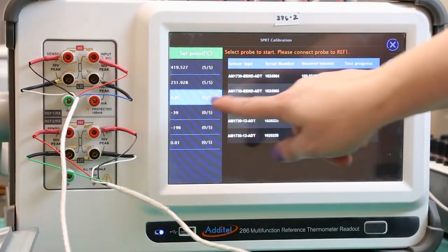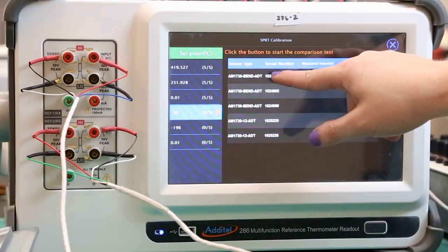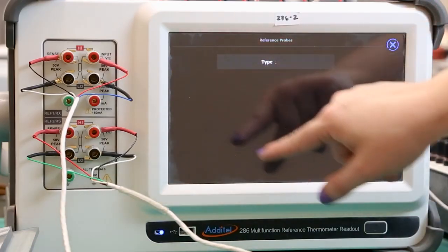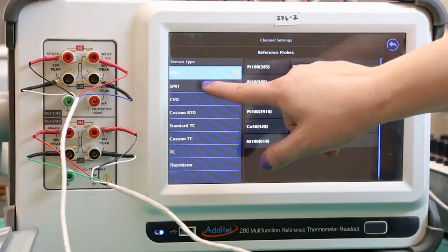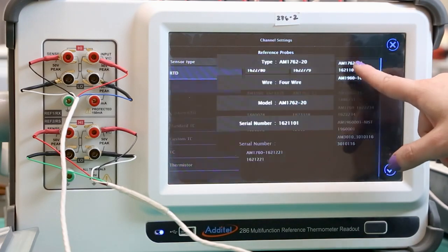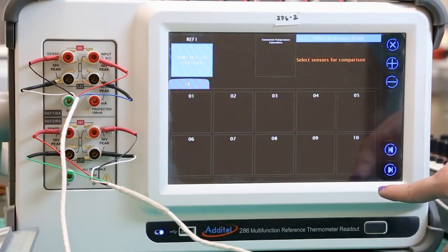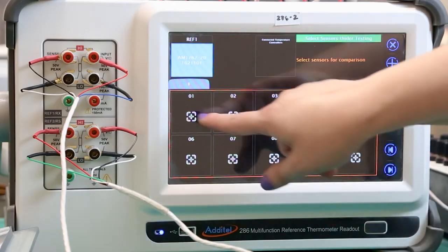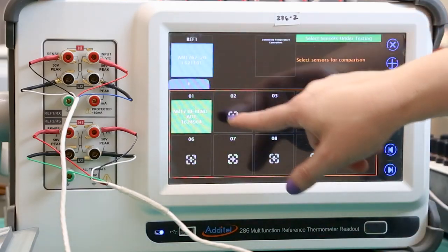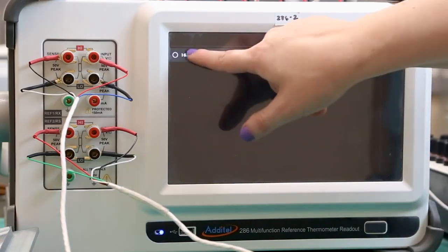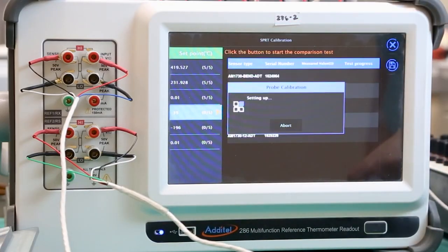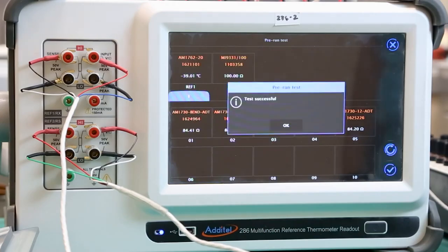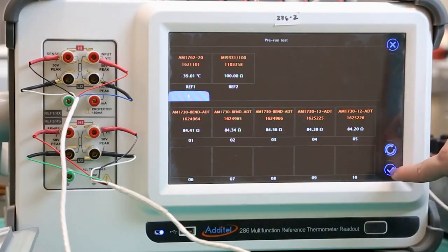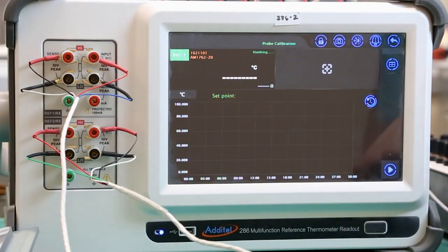Now we can add each of the probes for the automated measurement. Select the first probe section, then add the reference SPRT from a list of preset probes. Then press the next button and add each probe to be measured to the corresponding channels they're connected to. Press the next button again once finished. The 286 will now test each probe signal to ensure that they are working correctly. After that, press OK and the check mark in the bottom right corner to move to the next section. Once you select the play button in the bottom right corner, the test will begin.